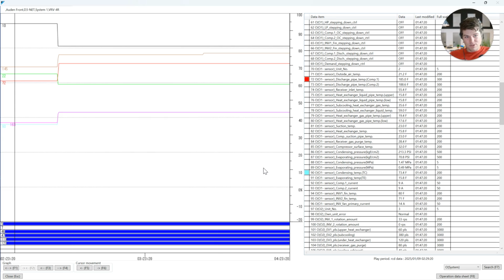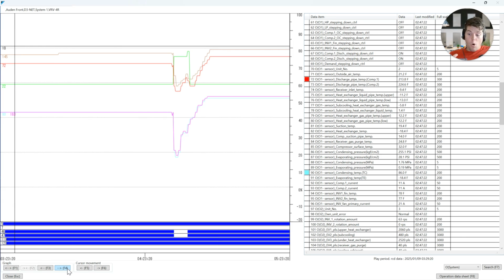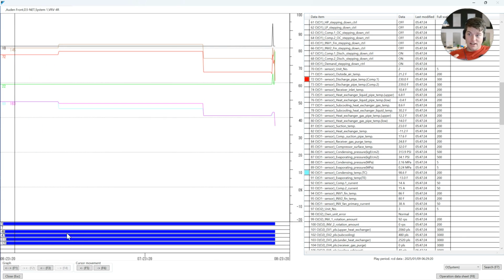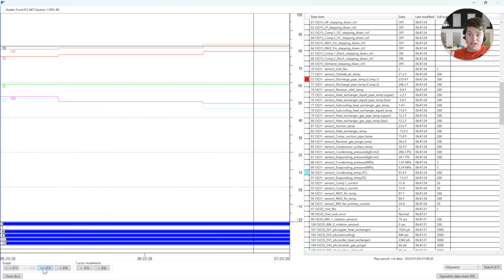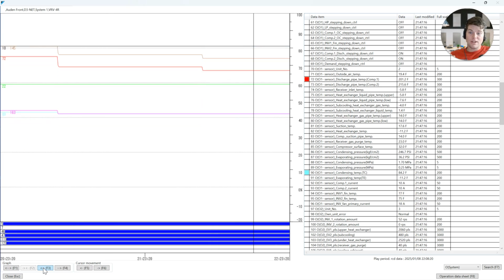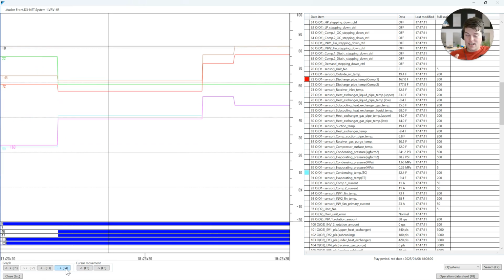Now, it's not just the oil return mode, it's the repeat oil return mode of a system that is already having high discharge superheat, that already has the wear and tear on the scroll plates, that is just going to put it over the edge, right? This compressor is just night shift, day shift, night shift, day shift, just burnt out. Someone give this compressor a break. That is discharge superheat over the set of data here. And as you can see, it stays pretty much the same across the board. So we know that discharge superheat is crazy high.